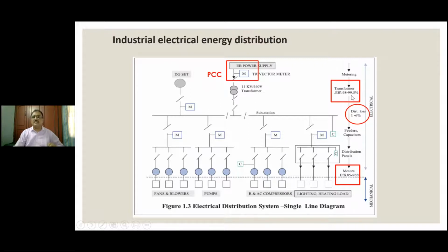These are some suggestions. The transformer is a highly efficient piece of equipment, with efficiency between 98% and 99.5%. Depending on the load factor, this efficiency could be closer to the nameplate. I have a slide; when we look at that, you will appreciate it. The distribution losses are between 1 to 6%. These are in the cables, in the bus bar, and in the switchgear, or even for that matter in the capacitors. So the distribution losses are estimated to be 1 to 6%.